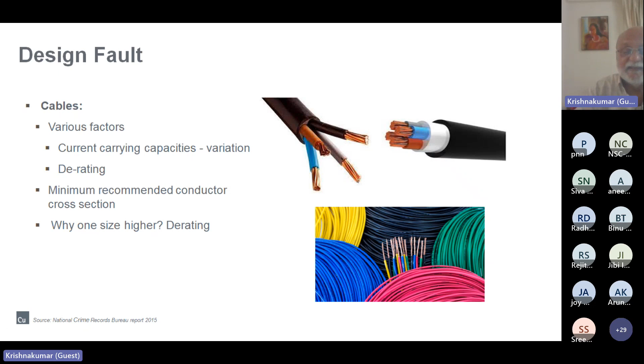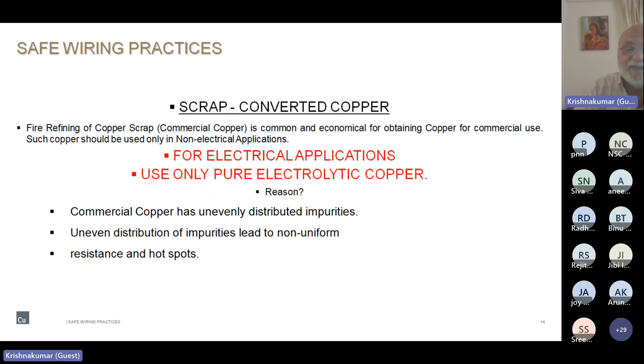So this is one principle which largely gets ignored, called derating. You have to derate the wires, because many times the cable sizes they proclaim in their catalogs can't carry even 50% of that capacity. What they show in their brochures is a conductor in the naked condition, in free air, and how much current it can take without heating up extraordinarily. But the actual situation is completely different.